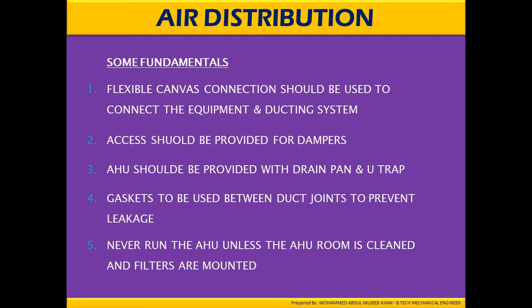Access should be provided for dampers. The air handling unit should be provided with drain and U-traps. Gaskets are to be used between duct joints to prevent leakage. Never run the air handling unit unless the AHU room is clean and filters are mounted.